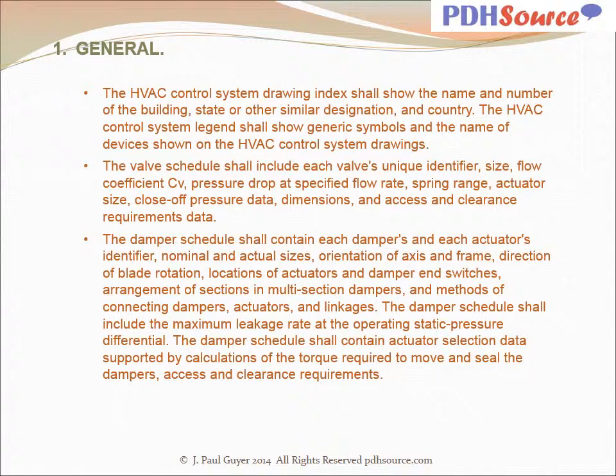The damper schedule shall contain each damper's and each actuator's identifier, nominal and actual sizes, orientation of axis and frame, direction of blade rotation, locations of actuators and damper end switches, arrangement of sections in multi-section dampers, and methods of connecting dampers, actuators, and linkages. The damper schedule shall include the maximum leakage rate at the operating static pressure differential. The damper schedule shall contain actuator selection data supported by calculations of the torque required to move and seal the dampers, access and clearance requirements.